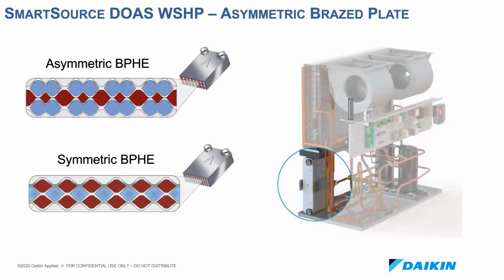The brazed plate heat exchangers used for the Smart Source DOAS units are not the same as the old brazed plate heat exchangers from the past. What's different is the asymmetric design. As the graphic shows here, the design has larger water passages, shown in blue, compared to the refrigerant passages shown in red. With this new design and minimum flow rates that we have established to ensure turbulent flow, it's very unlikely that fouling will ever occur. Compared to traditional coax coils of similar capacity, the brazed plate provides high efficiency and a low water pressure drop, and also costs less than the coax coil.